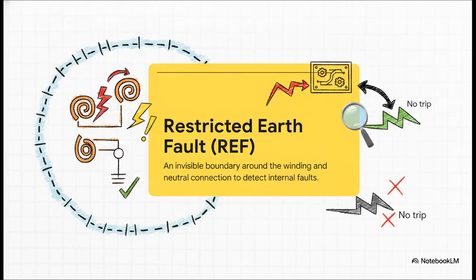And this dedicated close-up camera is what we formally call Restricted Earth Fault Protection, or REF for short. In plain language, an REF scheme basically draws an invisible electrical boundary, like a digital fence, around the transformer winding and its neutral connection. Any earth fault current inside that fence, bam, it trips the relay. Anything outside that fence, it flows right past without tripping it. It gives you true selectivity, completely ignoring external earth faults while offering extreme sensitivity to the internal ones.